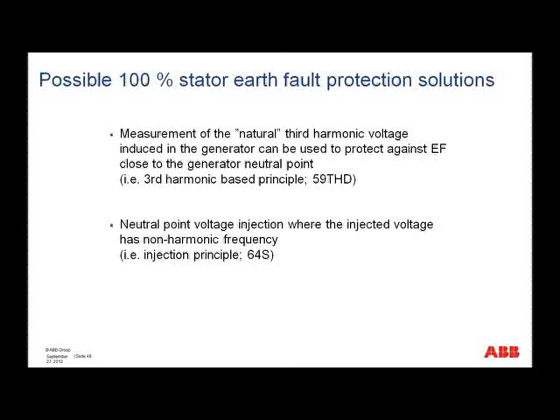And this is based on measurement of the natural third harmonic voltage induced in the generator. And the second one is the injection principle. Now, if you look at the third harmonic principle, you could say the plus here is the price. It would not cost really any extra money. But the minus here is that this method cannot detect an earth fault inside the stator when the machine is at standstill.